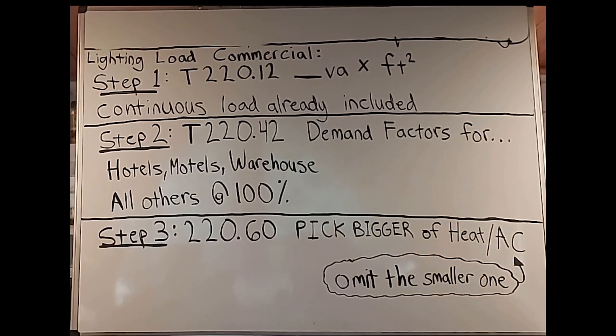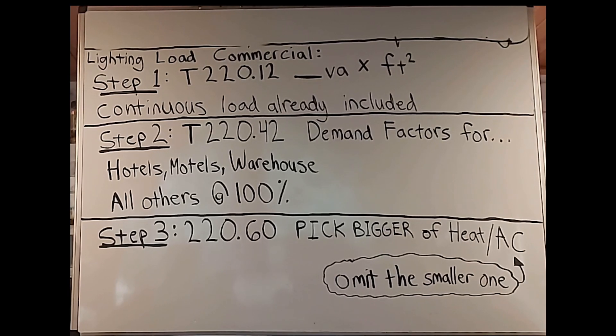Now we're going to step two. We have table 220.42, which has demand factors for hotels, motels, and warehouses. All other occupancies are at 100%, as shown in that same table where we have demand factors for dwelling units. Then step three comes from article 220.60, which tells us to pick the bigger of heat or AC and omit the smaller one. So if heat is bigger, we use that number and we don't use the AC number.